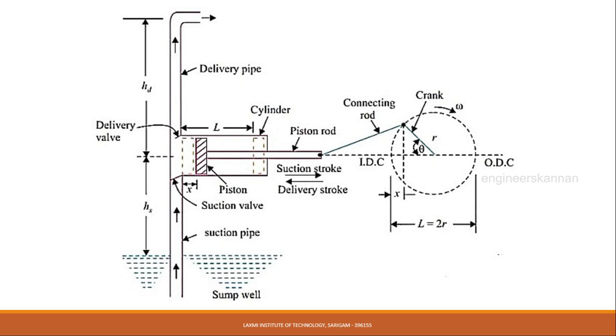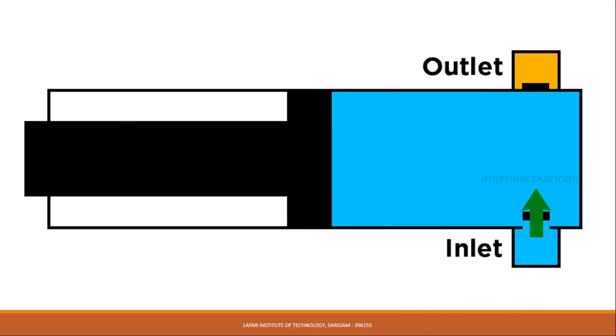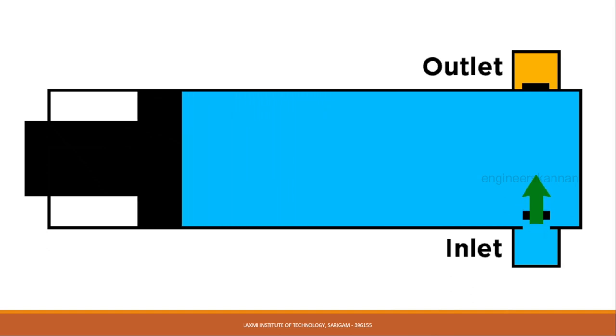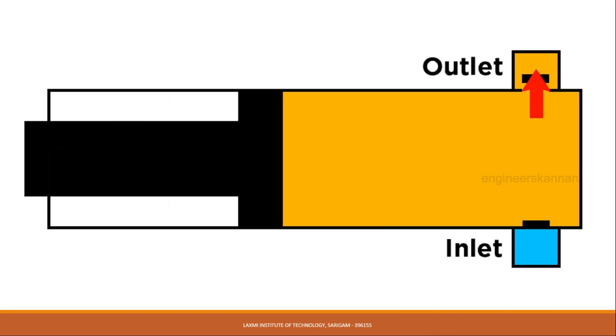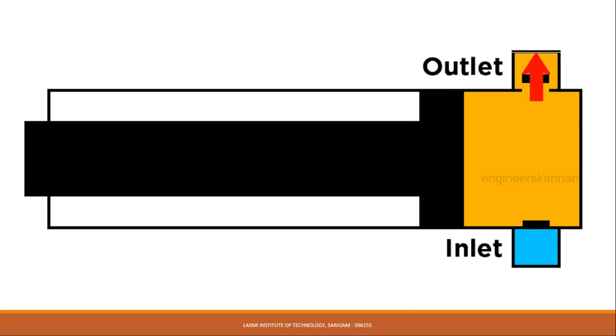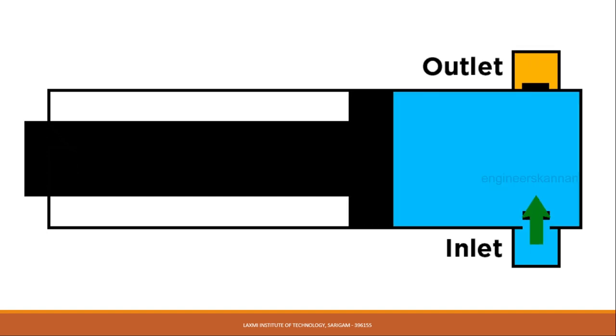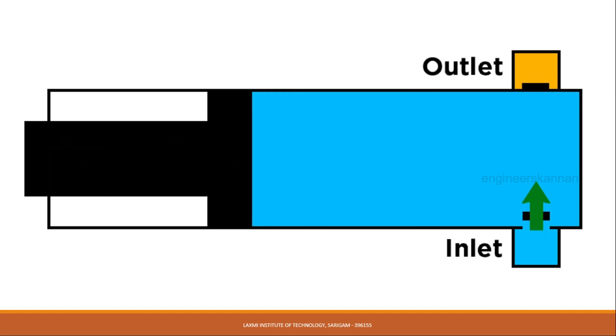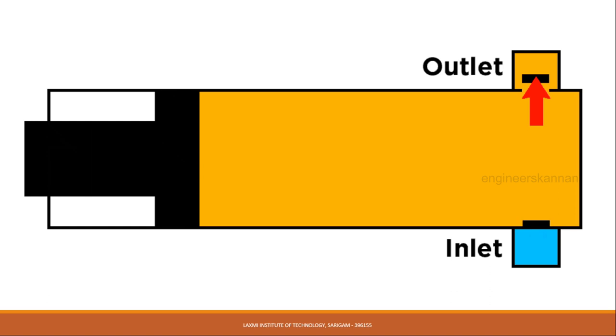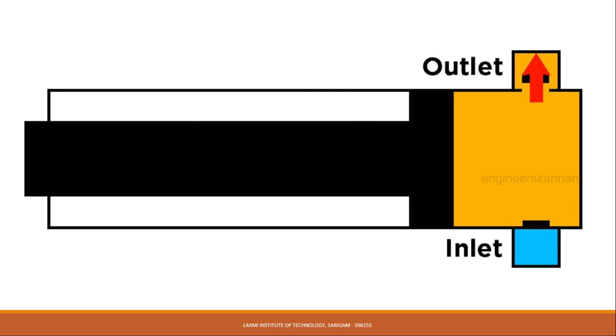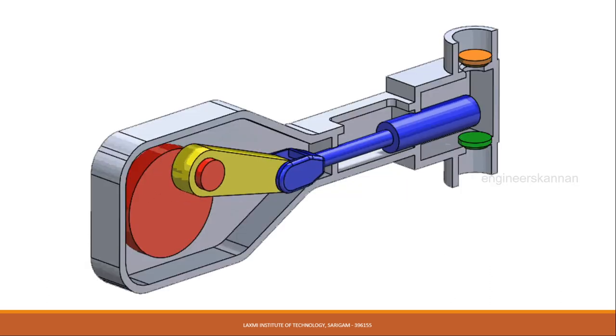Suction pipe and valve, delivery pipe and valve, cylinder, piston and piston rod, crank and connecting rod, strainer, and air vessel. When power is connected to the crank, it starts rotating and the connecting rod displaces along with the crank. This mechanical action creates vacuum inside the cylinder. When the crank moves, the suction valve opens while delivery valves get closed, and vice versa. Due to this action, water is pumped into the required place.